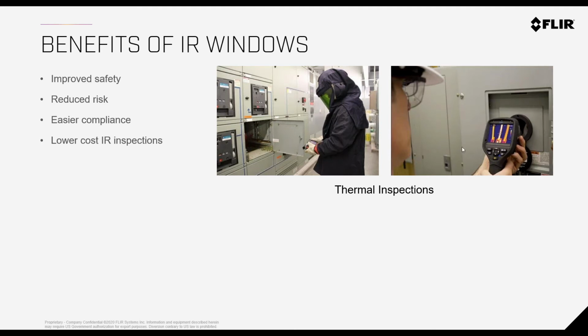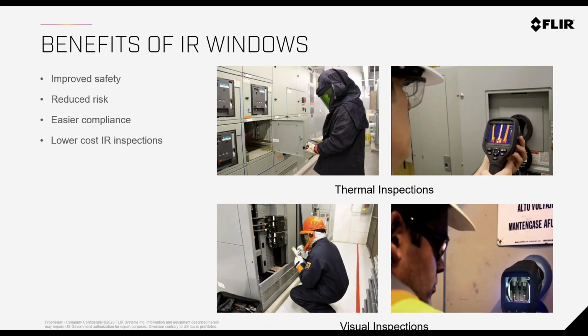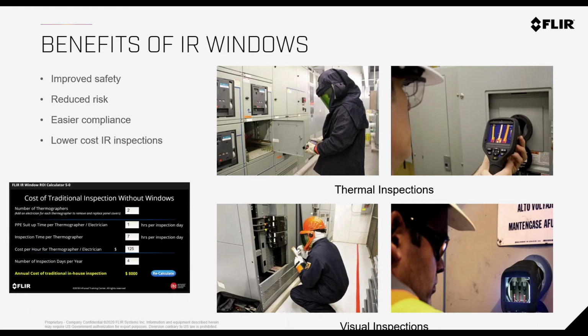The guy on the right, hey, what if you just cut a hole in there and put one of our windows in? Now I can take this with that panel still between me and the live energy. That's going to cause safety between us, it's that barrier between the energy. And then visual inspections as well. With all of our thermal imagers, you can do thermal imaging and visual inspections, so you can get both images on there.